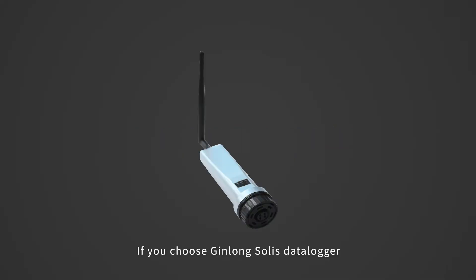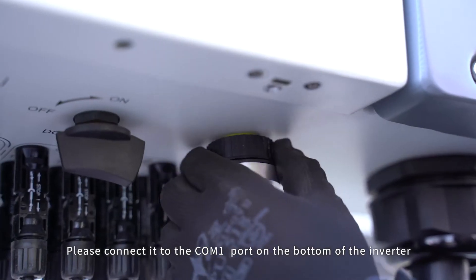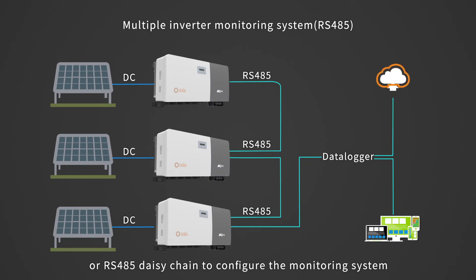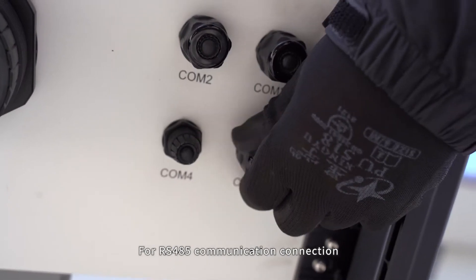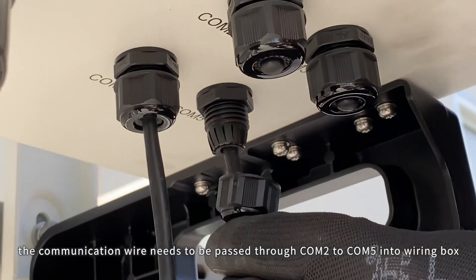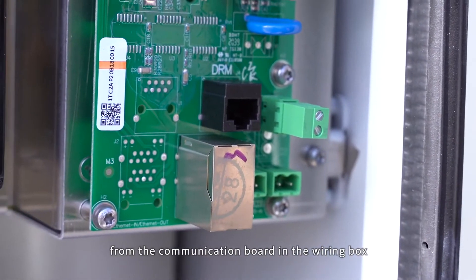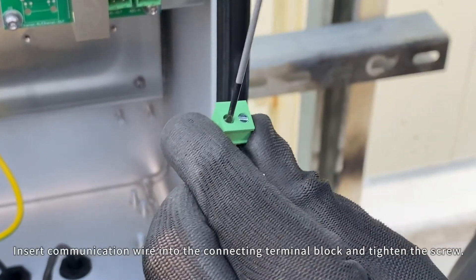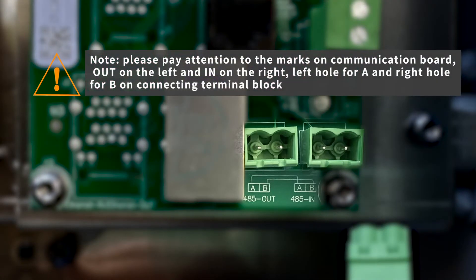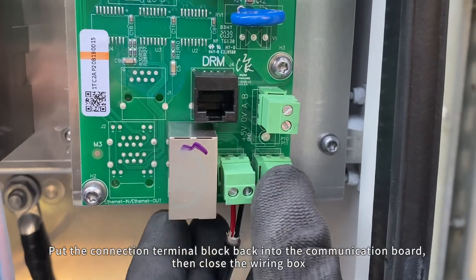Communication connection. If you choose Ginlong Solis data logger, please connect it to the COM1 port on the bottom of the inverter. You can also choose PLC method or RS-485 daisy chain to configure the monitoring system. For RS-485 communication connection, the communication wire needs to be passed through COM2 to COM5 into the wiring box. Open the wiring box, then remove the connecting terminal block from the communication board. Insert the communication wire into the connecting terminal block and tighten the screw. Put the connection terminal block back into the communication board, then close the wiring box.